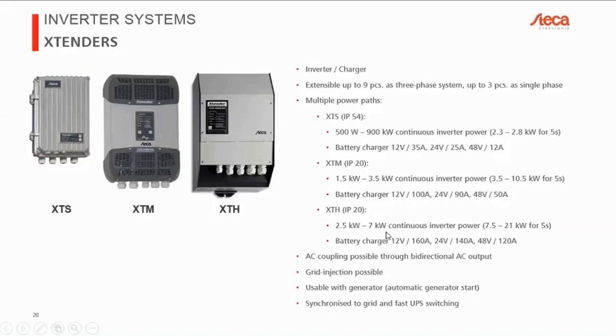And then finally, the XTH, those are the largest ones. They go all the way up to 7 kilowatts and 21 kilowatts for 5 seconds. So it's pretty much always times 3, except for a few special cases on the XTS. All the other ones can handle 3 times the nominal power in overload. Then, as I just said, we can do AC coupling because we have a bidirectional AC output. Grid injection is possible. So when the battery is full, for example, we can inject excess energy into the grid. We can use this with a generator. And also here we have relay contacts on the XTM and the XTH. For the XTS, there's a relay module which you can buy separately, so you can add that as well. We can use these contacts to control a generator, for example, but we can do much more as well.